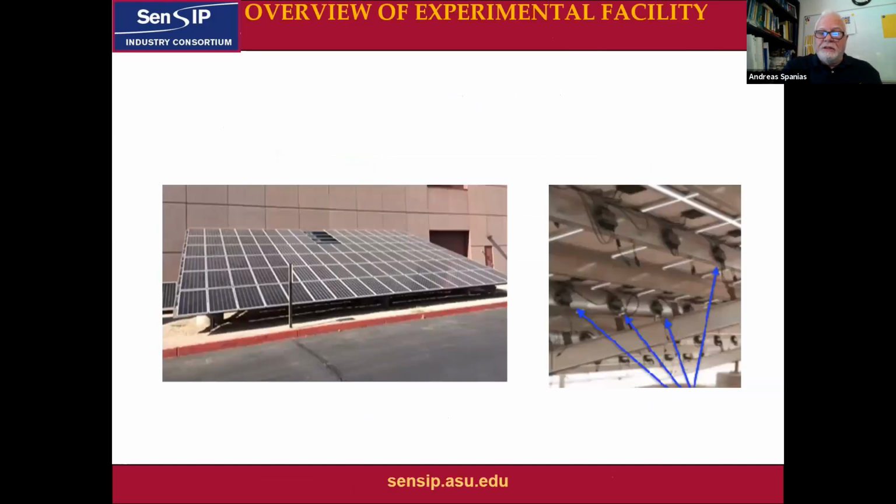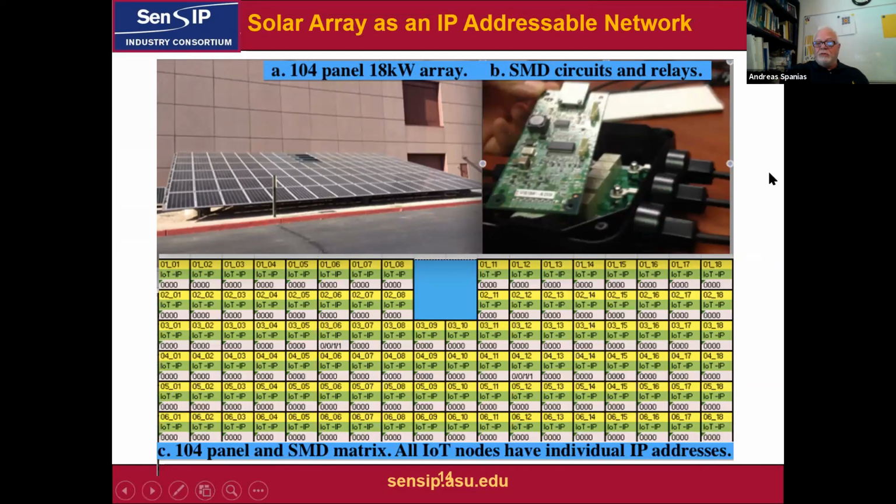This shows you our experimental facility at the ASU Research Park. And we have built here, with some support both from ASU and from sponsors, this facility with 104 panels. And what I'm showing you here are the smart monitoring devices that have the sensors, the actuators, the microcontroller, and the radio that enables them to communicate with the internet. So through secure internet, you can monitor what each and every panel is producing here. And at the same time, you can change the type of connections. The default connection is 8 series strings that consist of 13 panels each, but you can change them into different topologies based on instructions that we obtain from shading data and from the neural net that is continuously optimizing this.